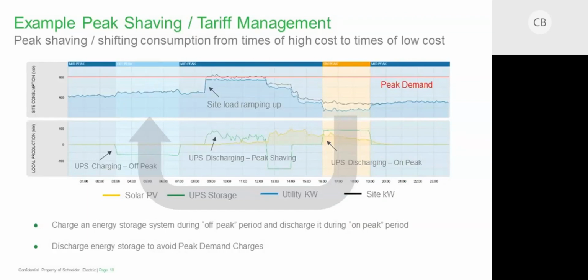All right. So this is an example showing a load profile in a building, and it looks very complex and confusing, but really it's very simple. On the right third, you see a yellow section. That's the on-peak. Utility companies have on-peak hours and off-peak hours, and during the on-peak hours that kW demand charge is extremely high. Typically, in the late afternoon hours, you're going to see these peaks. You're going to be on an on-peak demand charge, and that's when you go to a battery. Or in a microgrid solution, you may go to the battery on the UPS. It may be a battery energy storage solution. You may transfer to some other distributed energy resources like solar, a fuel cell or a wind turbine. There are all kinds of options there.